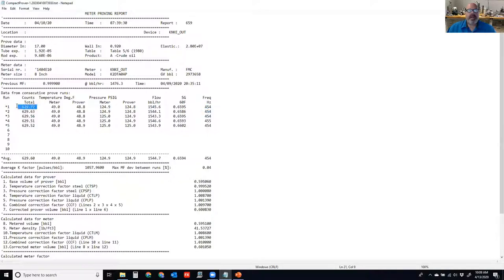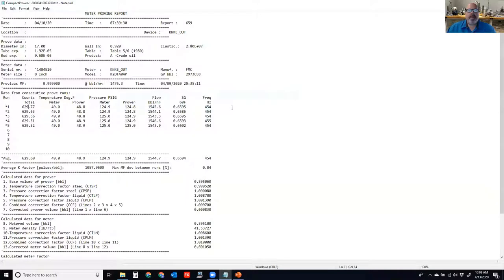What I really care about is the pulse counts — total pulse counts within each run. Based on those counts, I come up with repeatability. I don't care about temperature and pressure for each run in determining repeatability. Repeatability either looks at counts (depending on setup) or looks at a meter factor derived for each run and compares repeatability between those meter factors.